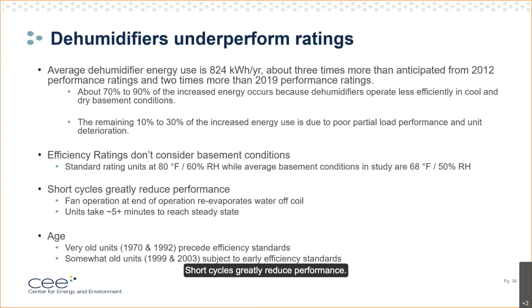Short cycles greatly reduce performance. Fan operation at the end of the cycle re-evaporates water off the coil. That's the main effect, but units also take a long time to warm up to reach steady state.